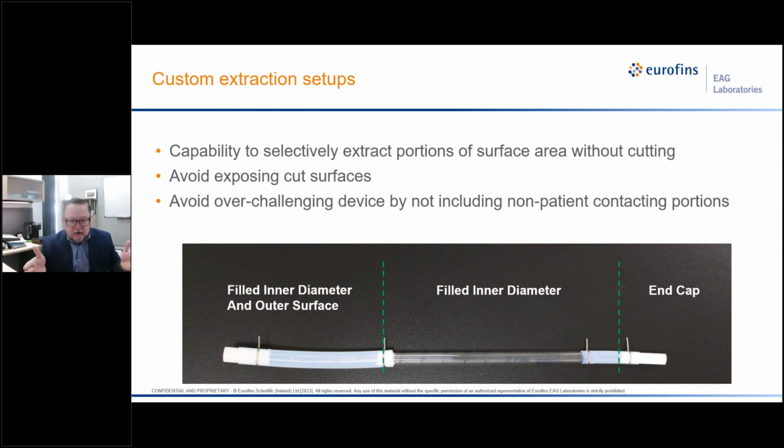So say a 12-inch long device, but only 6 inches is in patient contact, if you can justify that that whole 12 inches is manufactured in the same fashion, exposed to the same processing aids or cleaning agents or sterilization technique, and document that, you can treat it as two devices. And then effectively, if you use the same amount of solvent, you double your AET. So being creative around those strategies, and trying to defend and justify it, is a really effective way of improving your chances of success.